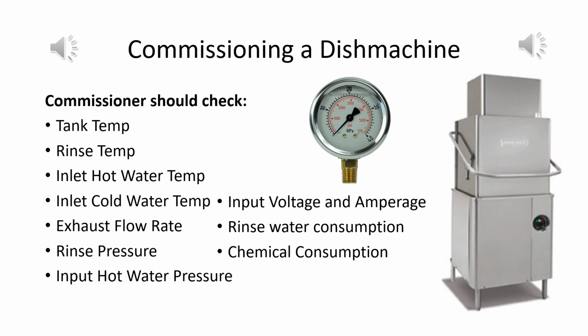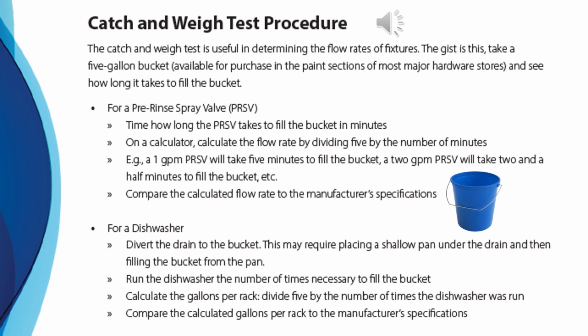The inlet cold water temperature needs to be checked for heat recovery dish machines because the ventless function of heat recovery machines can sometimes be compromised by inlet cold water temperatures over about 80 degrees. The exhaust flow rate needs to be matched to the exhaust fan speed for adequate ventilation of the dish room, and the rest of the bulleted items in this list need to be checked for proper commissioning of the dish machine. The catch and weigh test is a useful method of determining the flow rate of fixtures and is an important part of commissioning a new hot water system or installing new fixtures. This test is performed by measuring the amount of time it takes to fill a 5-gallon bucket with a fixture. Example procedures for pre-rinse spray valves and dishwashers are included on this slide.